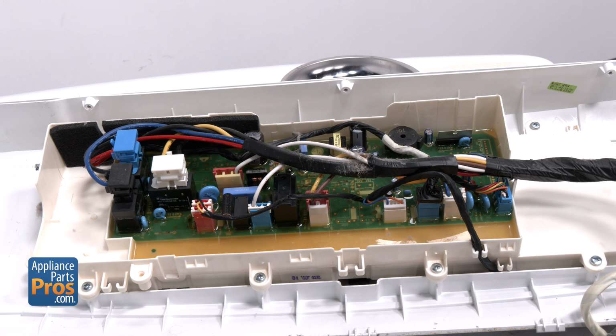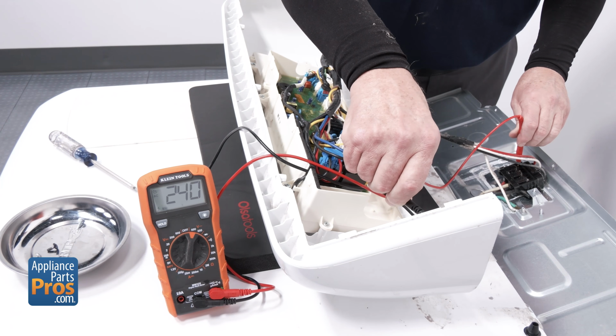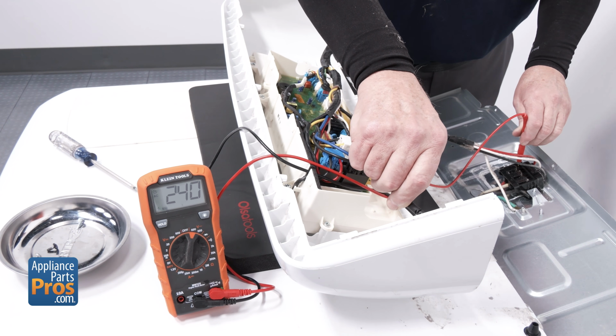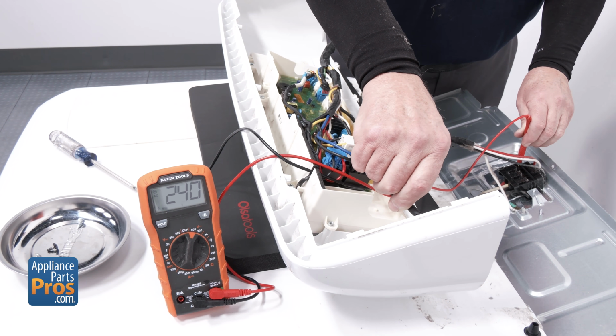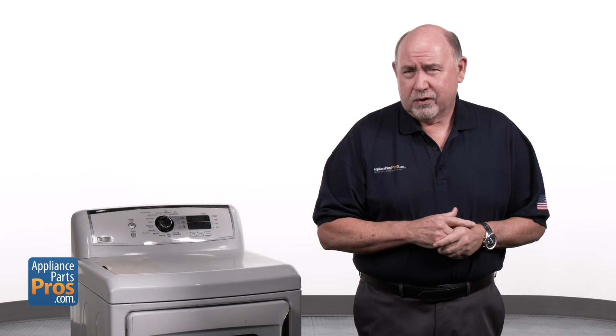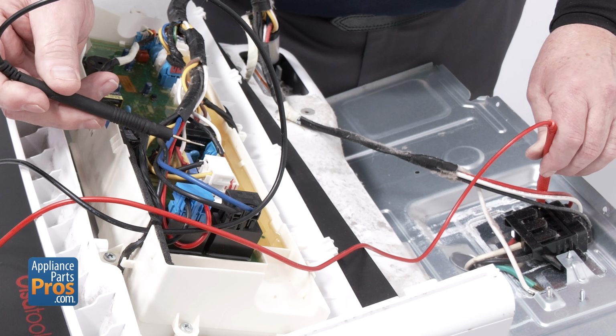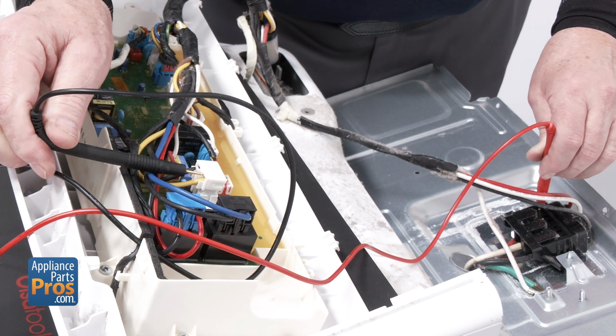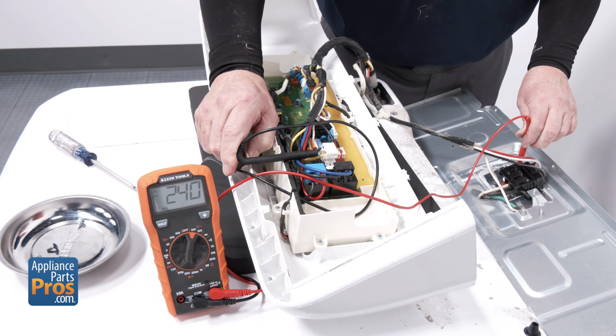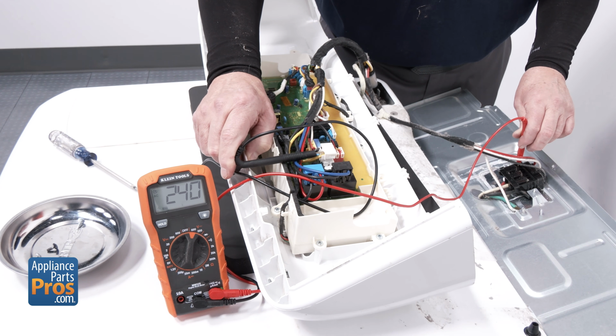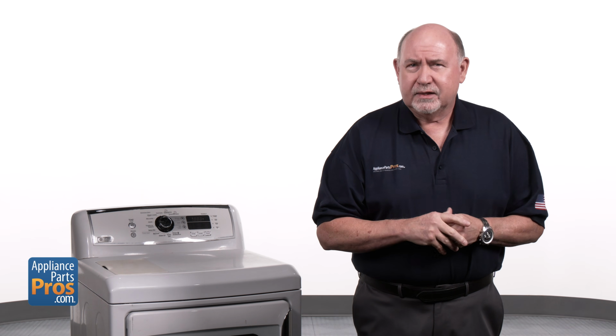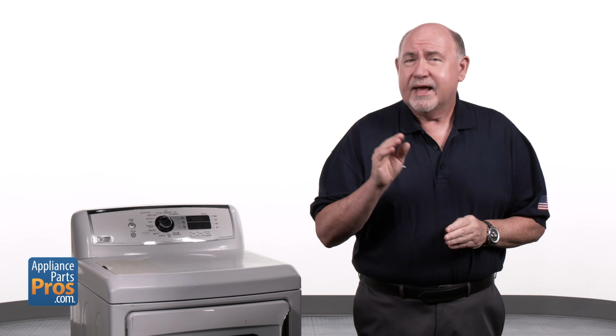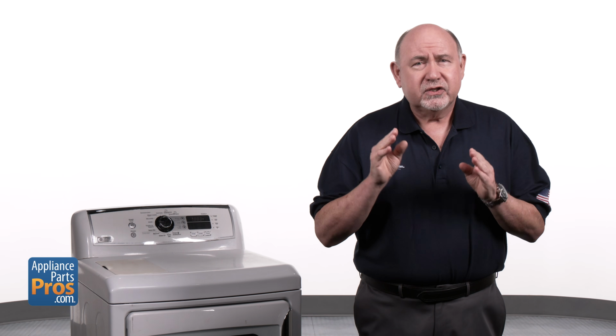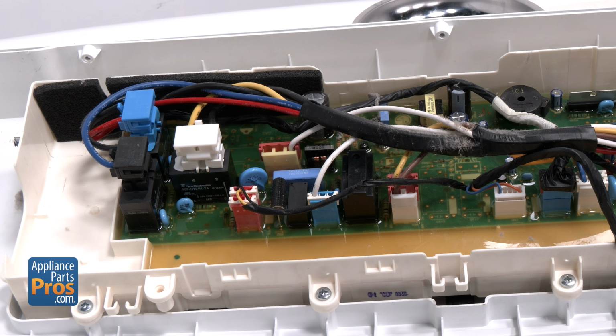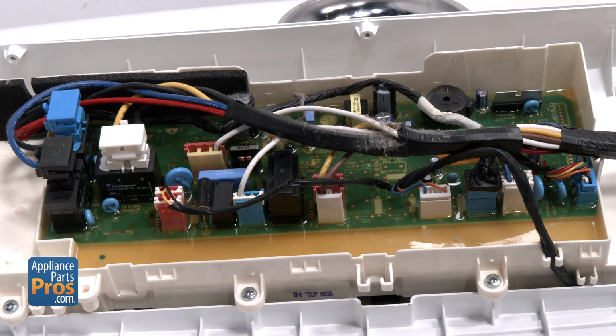Now take one probe and place it on the blue wire at the black relay. Put the other probe on L2. You should get 240 volts AC. That's your outer coil circuit. Next, move to the yellow wire at the white relay. Again, check to L2. You should also see 240 volts there. If you're not getting those readings, that tells you one of the relays isn't closing. It's not sending voltage to the heating element, and that means the control board's failed.